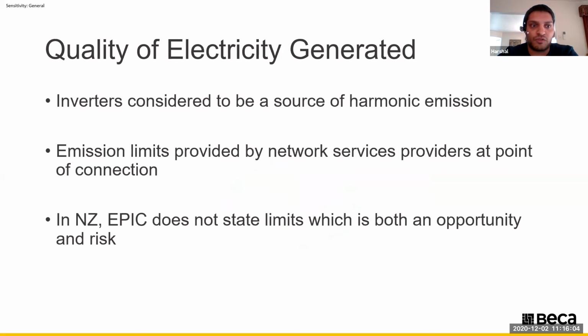Regarding quality of electricity generated, harmonic voltage distortion is becoming increasingly common due to inverter systems, which are considered a source of harmonics because they are switching power electronic devices. In Australia, the transmission network service providers actually provide the emission limits at the point of connection, so it's quite transparent for developers regarding the performance you need to demonstrate as part of the grid connection compliance process.